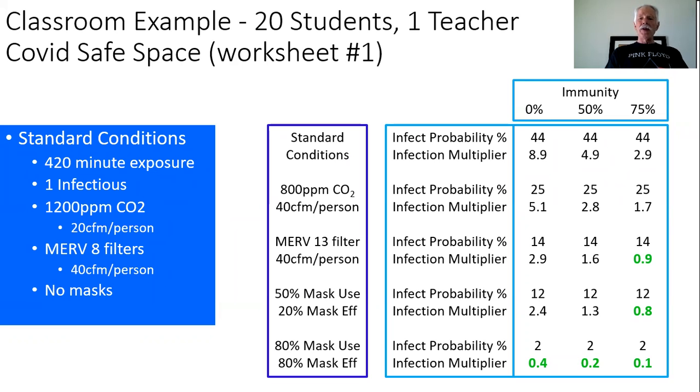And the typical building that we're assuming would have a carbon dioxide concentration level of about 1,200 parts per million. And as you follow our video on carbon dioxide, you'll see that that indicates how much fresh air is coming in. And that's an important factor in diluting and reducing the concentration of contagion that's in the room if there's an infectious person.